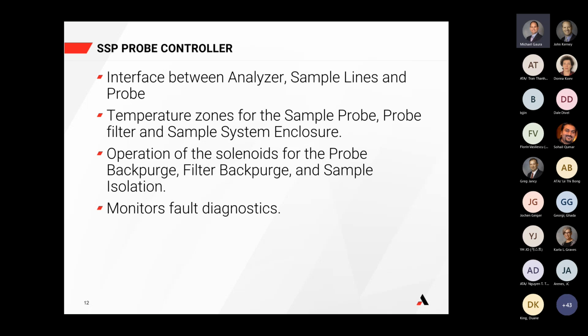And again, I hope you can all see my mouse. I'm going to move this around a little bit. And essentially, the probe controller just pulls everything together. It's sitting in between the analyzer, the heated sample lines, and the probe that Rod just walked us through. And it's responsible for managing the temperature zones of all the components that Rod mentioned, but also it's working with the analyzer to manage its temperature as well as the heated sample lines.